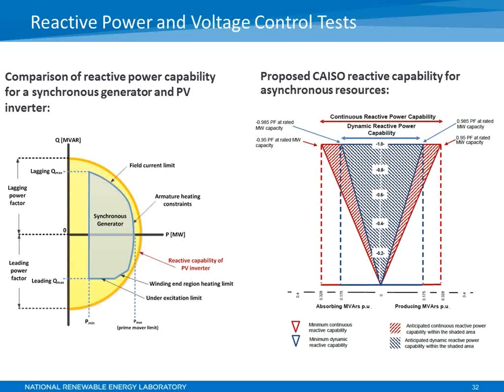So voltage in many power systems, in the bulk power system, is normally regulated by generator operators. And this type of service is typically provided with voltage schedules set by transmission operators. Growing levels of penetration of variable wind and solar generation are leading to the need for them also to contribute to power system voltage and reactive power regulation, because in the past, bulk system voltage regulation was provided almost exclusively by synchronous generators, and this landscape is changing fast in many places in the US.